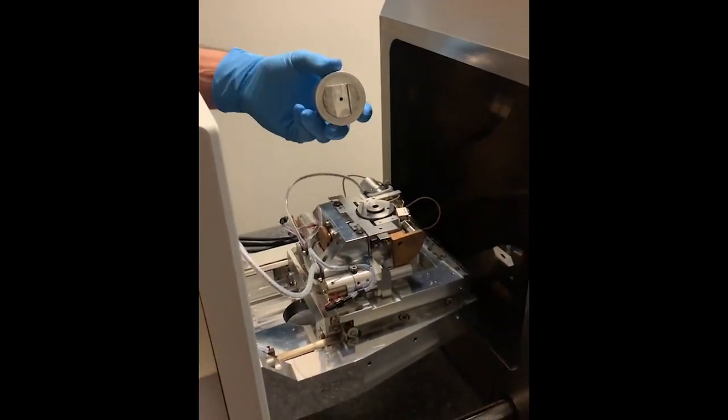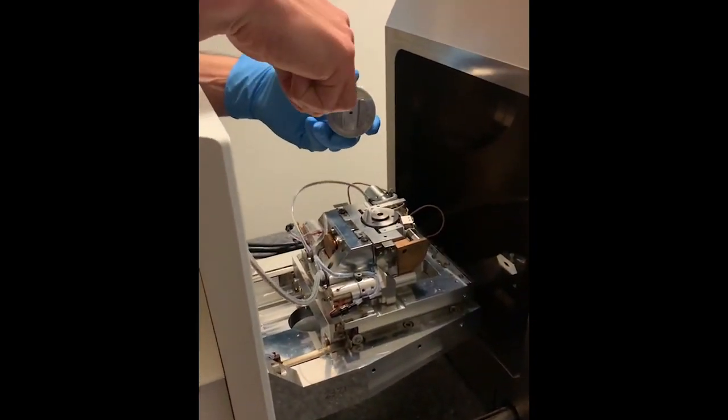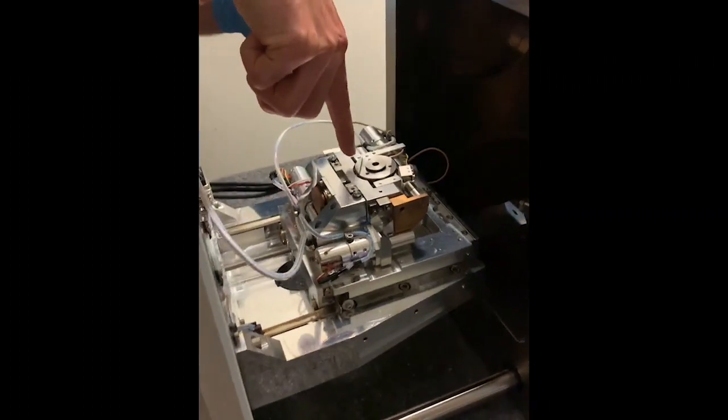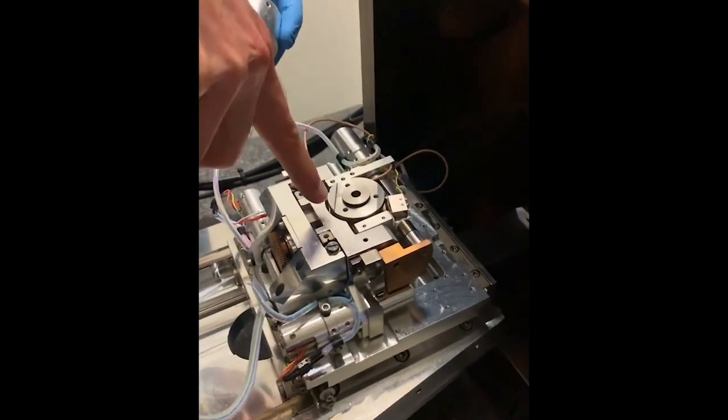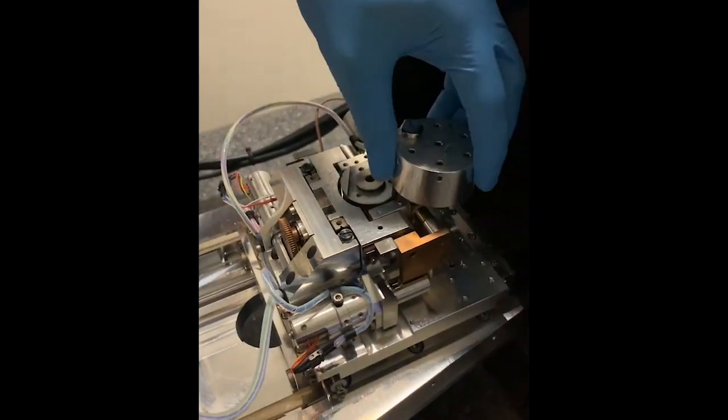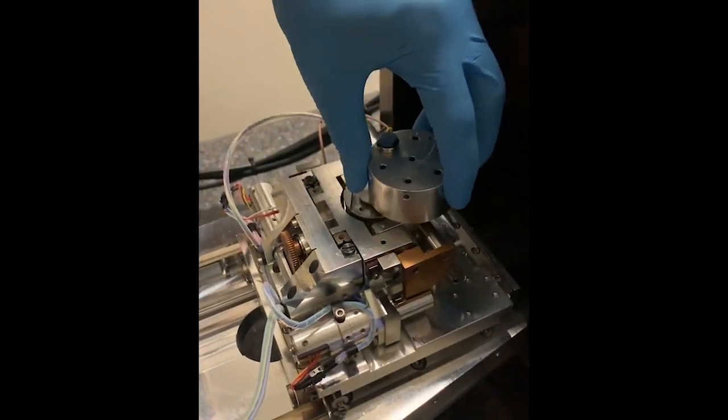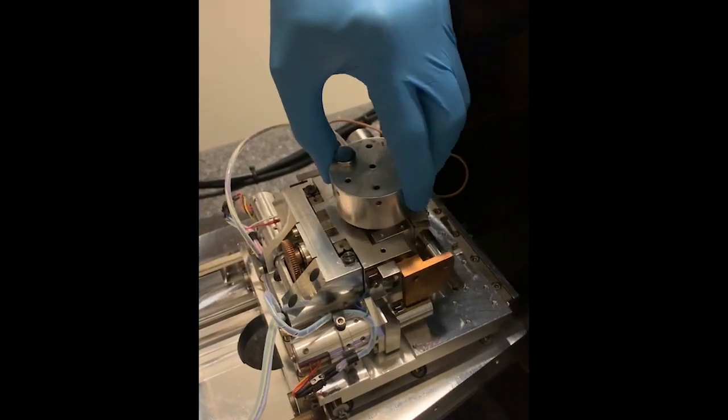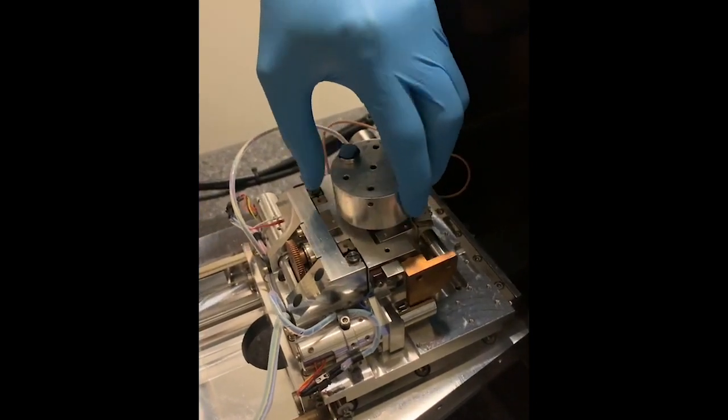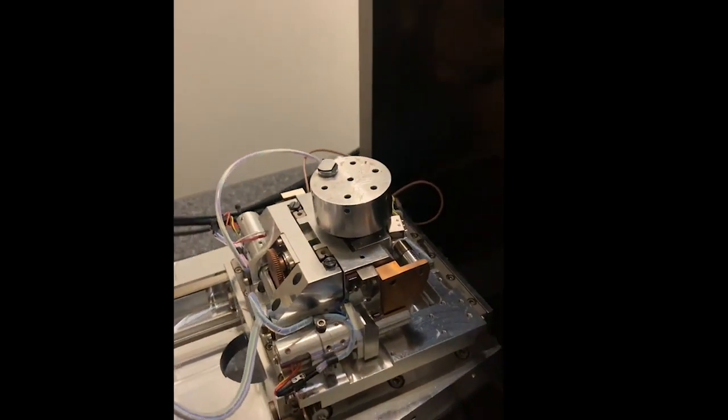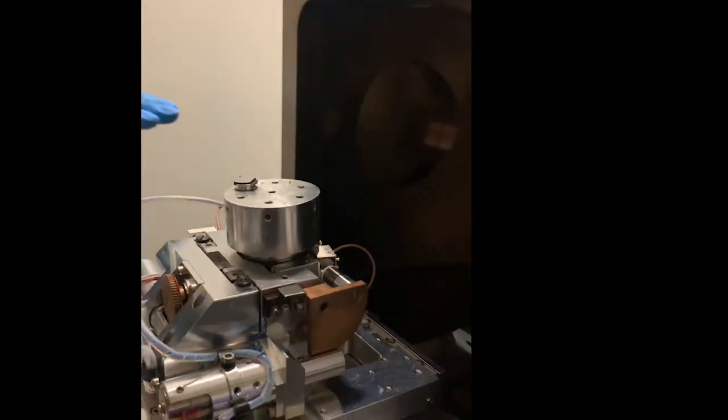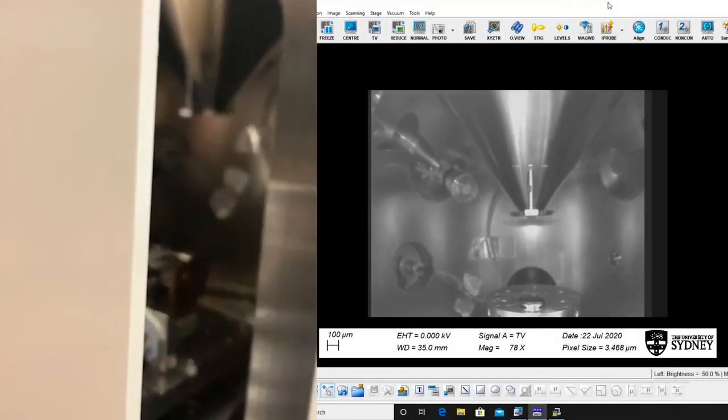Slide the holder onto the stage mount. The dovetail on the holder base has a flat edge and this should locate against the stop bar on the stage. Carefully close the chamber door while watching the live chamber view on the monitor to make sure the stage and specimens are not going to hit the column or EDS detectors.